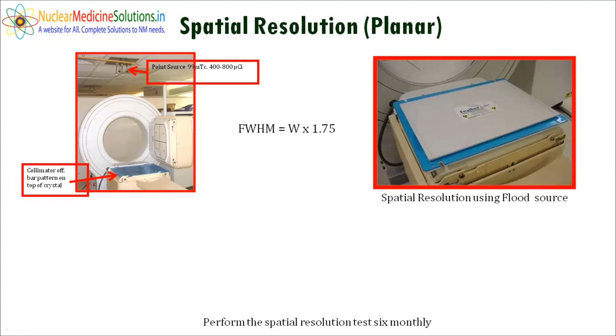So the spatial resolution test can be done. Again, there are two types of spatial resolution, as I told you, intrinsic and extrinsic. Intrinsic spatial resolution can be measured by using a point source and a bar phantom, keeping the point source at 5 UFOV from the surface of the detector. And to check the extrinsic resolution, you can use a flood source of cobalt 57 or technetium 99m and a bar phantom, and then you multiply the minimum bar space which is resolved by the gamma camera by 1.75. It will give you the FWHM, that is the spatial resolution of your camera.